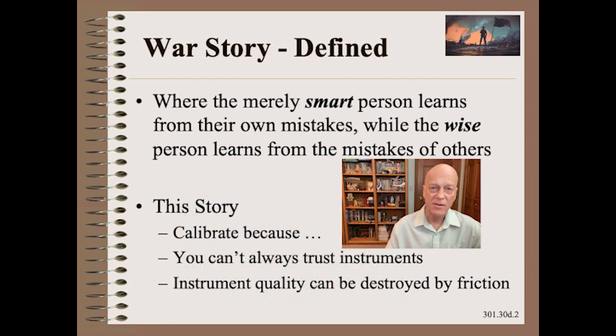In this war story, we learn three things. First is to check and recheck calibration. Second is you can't always trust instruments, a theme we will return to more than a few times again in this series. Third, instruments that have moving parts can be destroyed by friction. This could be as simple as a pressure gauge, or as complicated as a servo valve, or even more complicated as a loading system such as used for nips and converting.